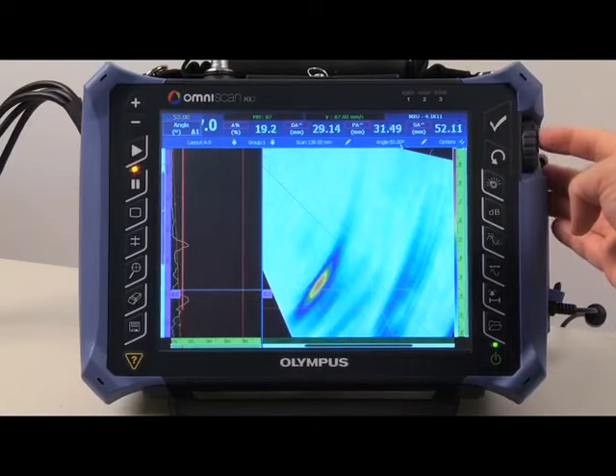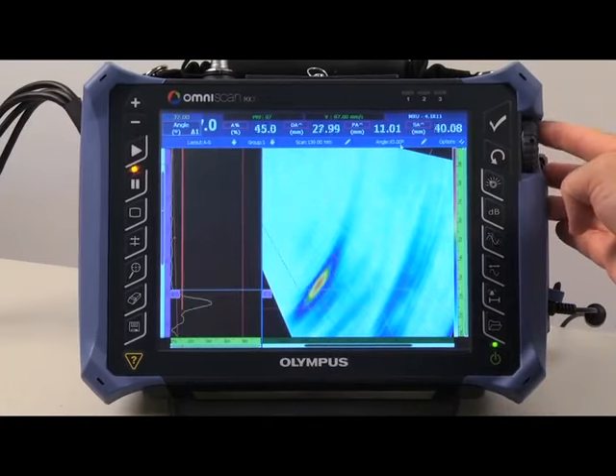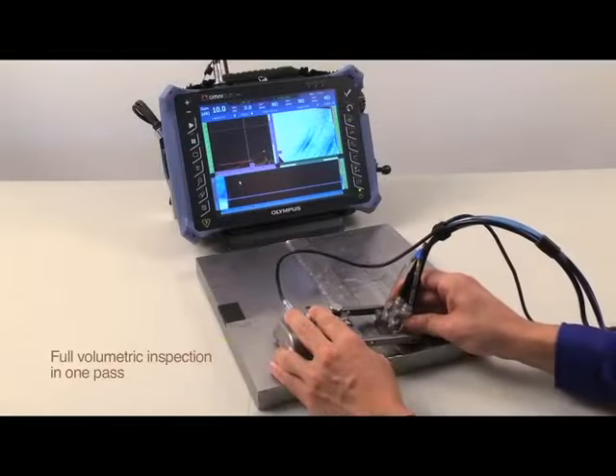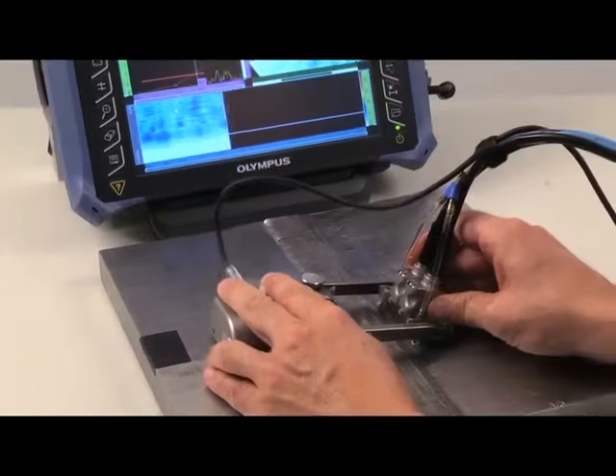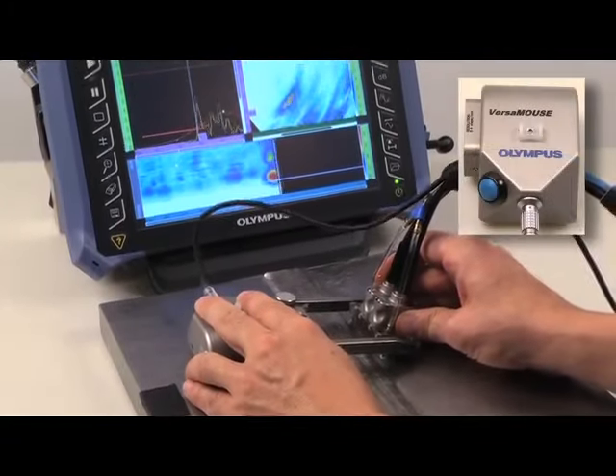In this example, programming a 30 to 80 degree longitudinal wave S-scan provides full volumetric inspection of the austenitic weld in one pass using the Olympus VersaMouse scanner.